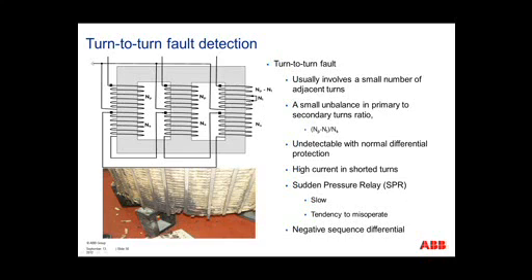is, unfortunately, the differential does not see this change in current because the transformer forces the currents to be balanced. However, our turns ratio has now changed, giving us essentially a hot spot inside the transformer. The sudden pressure relay will eventually see this condition. However, if it does, it's typically too late and it has a tendency to misoperate. So our solution for turn-to-turn fault detection is what we call a negative sequence differential.